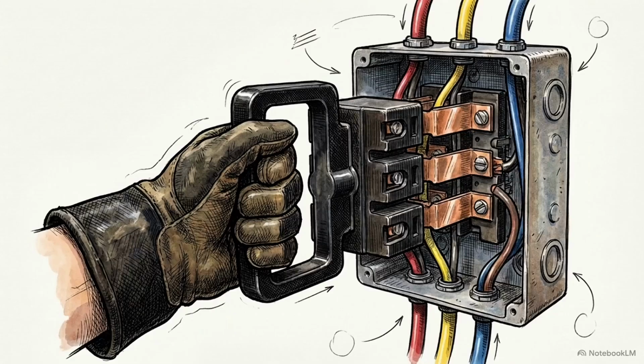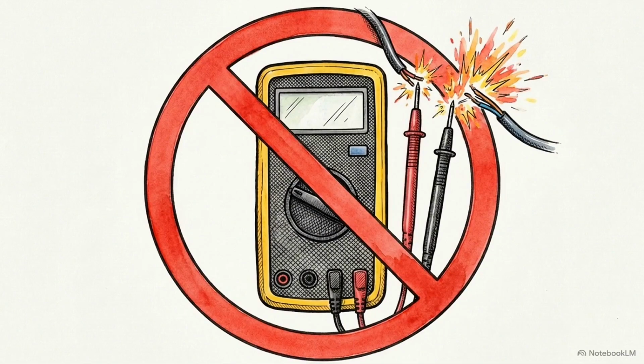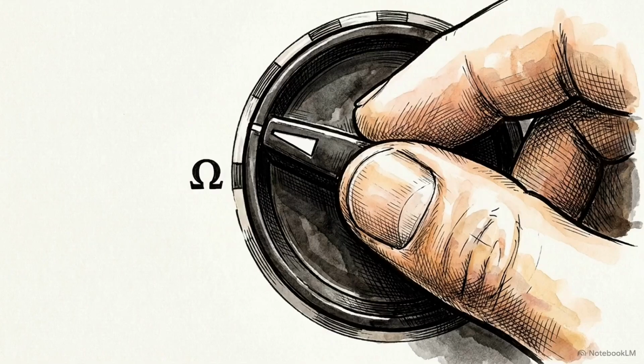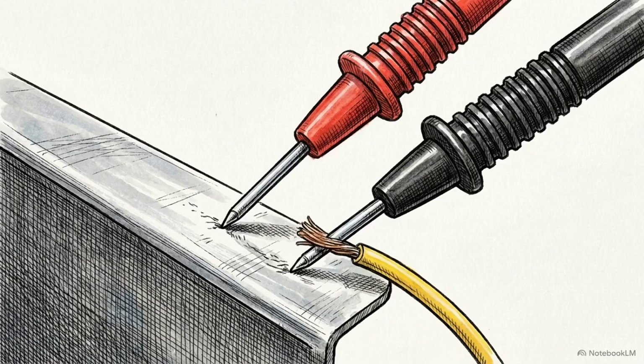Once you have identified the specific failing branch, turn off all power to the system entirely. Never test for resistance or continuity while power is still applied to the circuit. Doing so will destroy your multimeter and compromise your readings. Set your meter to resistance or ohms mode. Test each individual conductor in the failing branch to the common wire. Test each conductor to ground, and measure the resistance of any disconnected coils directly.